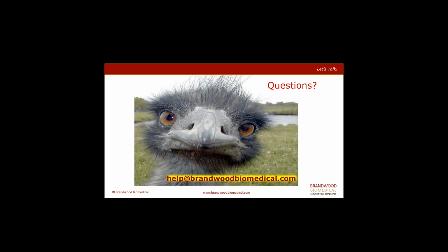I think to a great extent, yes, they are becoming more similar, but from what the draft standard has identified for the 2016 release, it will become even more focused on risk-based thinking and the evaluation of those risks within each process, not just in the overall risk management of the device and processes identified in the manufacturing of that device, but basically all the elements within 13485 will become very much risk-evaluation based.